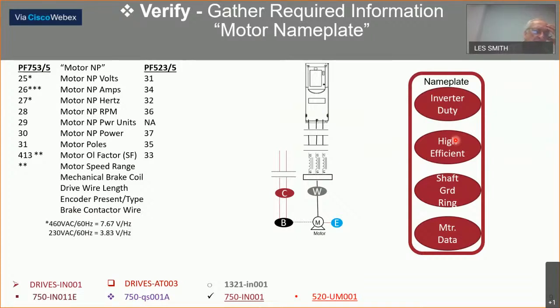Oh, here's the note. This is your volts per hertz. On a 460 volt motor, 60 hertz, your volts per hertz rating is 7.67. That is where your performance is based on. You've got to get the motor nameplate data in there in order to get maximum performance. If you're 230, it's half that. That's very important to understand and to know.